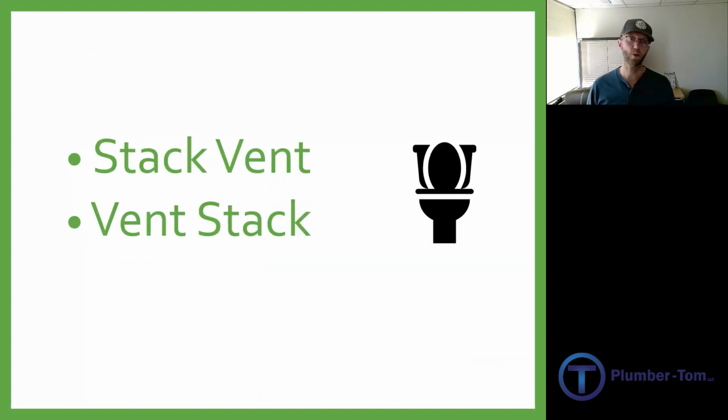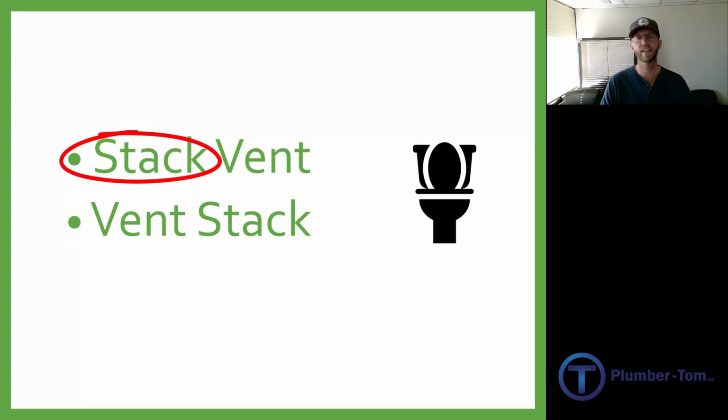Let's jump back really quickly to our vent definitions from chapter 2. These are two terms that may be confused because they're the same words in a different order. We have this stack vent and the vent stack. Which is which? Well, you need to know because we're just about to talk about the requirements for these. So let's focus in. A stack vent is a vent that comes off of drains at the top of a drainage stack. The key here is to take the first word of these sets and put it first. And that word is going to indicate what is happening. So if it's a stack vent, you have a drainage stack and there's a vent on the top.